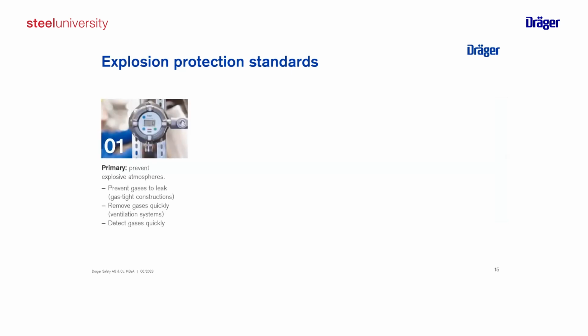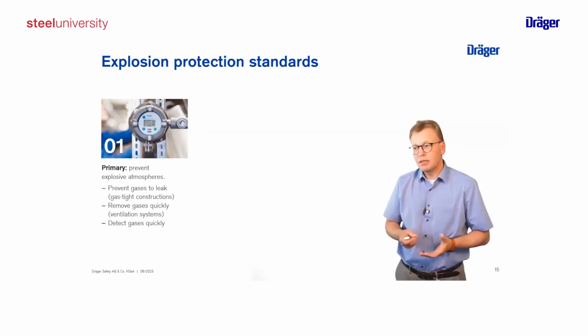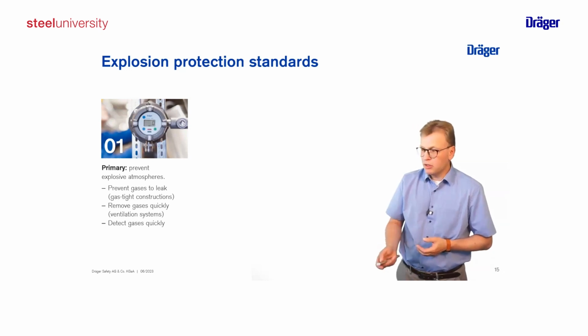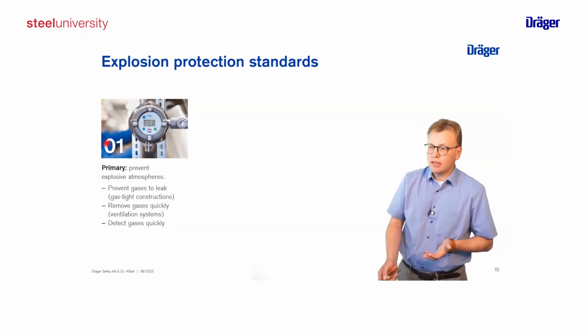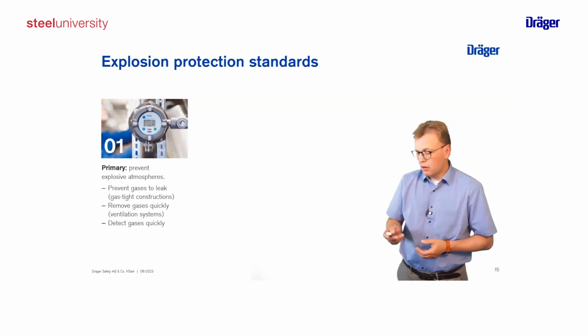Okay, so we want to do explosion protection, and what we always do there is we speak about primary explosion protection. So the idea is always first, we want to prevent explosive atmosphere. Or put it the other way around, you're dealing with substances which can form an explosive atmosphere, but maybe there are possibilities to prevent them from reaching a level where there is an explosive atmosphere. And this can be achieved by designing your processes or your equipment to be gas tight, so the probability of a leak is very low. Or you use ventilation, so you remove gases out of the application, or you use detection to pick these up to activate measures to keep the area free of explosive atmosphere. So this is the primary. So we want to prevent the formation of explosive atmosphere.